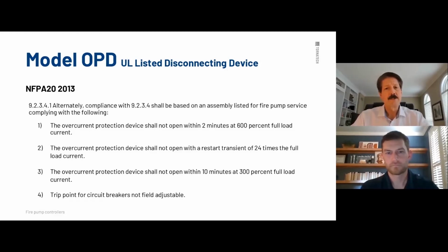Secondly, and this is huge, a restart transient of 24 times full load current. Not 5, not 10, not 15, but 24 times transient. That's a huge surge spike. So that will not trip offline. The third, overcurrent protective device shall not open within 10 minutes at 300%. And the last item is you are not allowed to have a field adjustment. That's the 4 key criteria for the OPD.